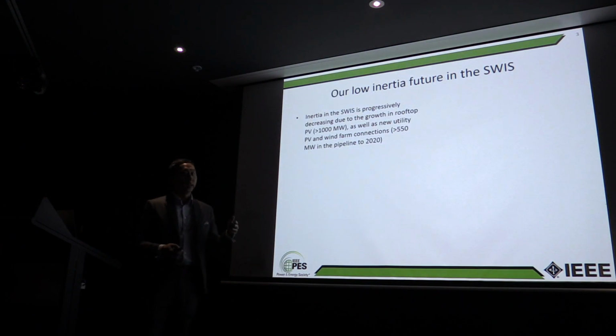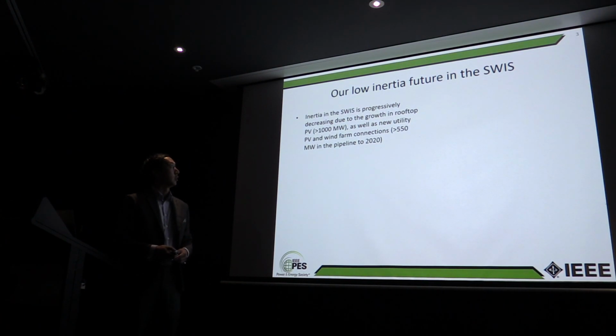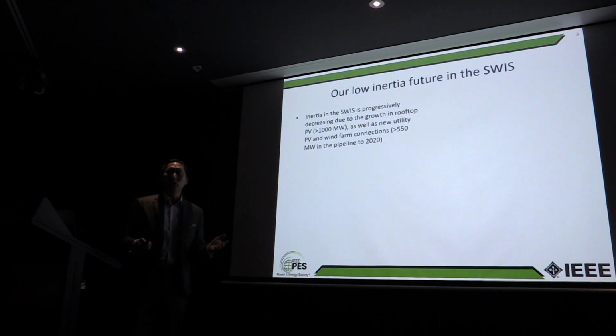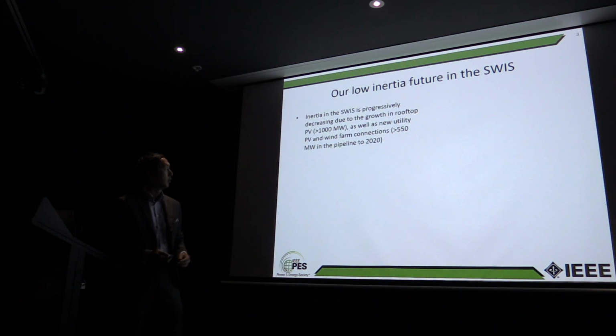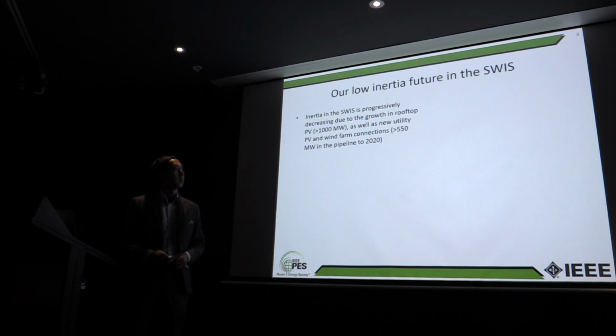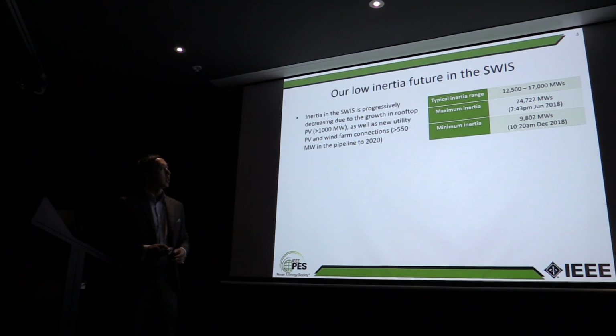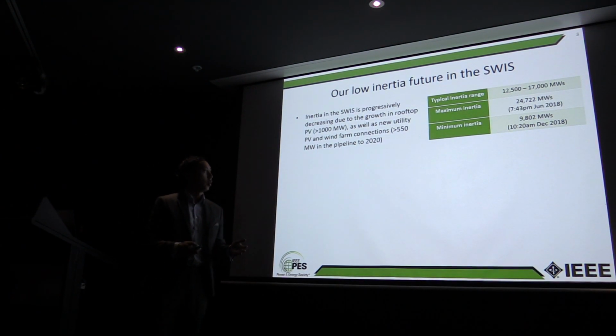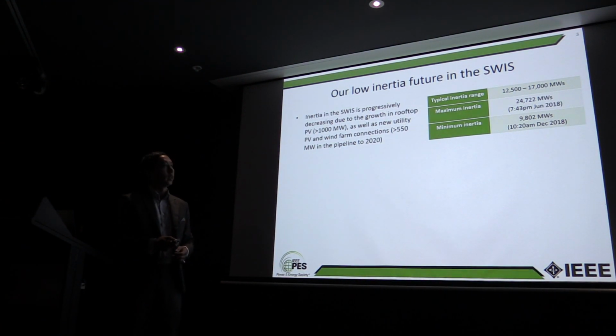So progressively, the inertia in the SWIS is actually decreasing with the growth of rooftop solar primarily. There's more than 1,100 megawatts, I think, now, of rooftop solar, as well as new utility wind and PV farms being connected. So by the end of next year, there'll be more than 550 megawatts connected to the system.